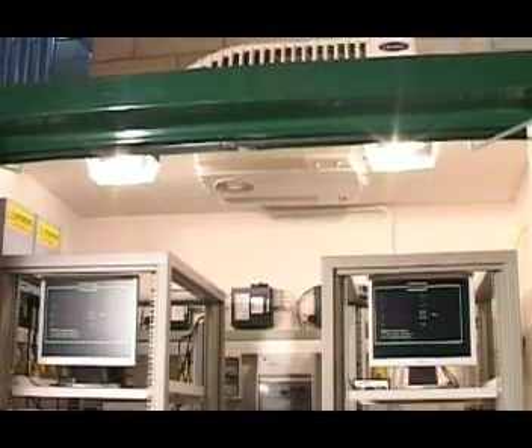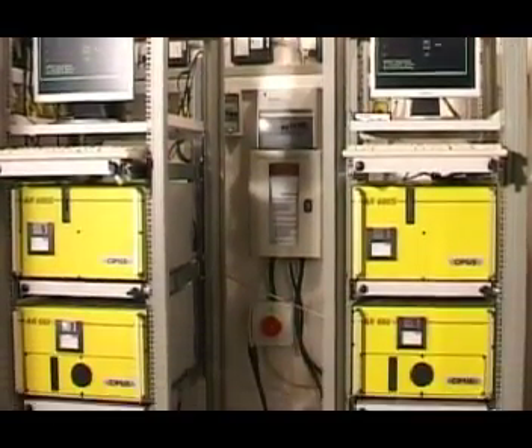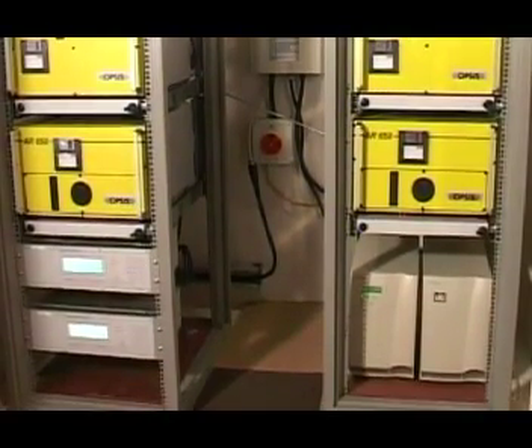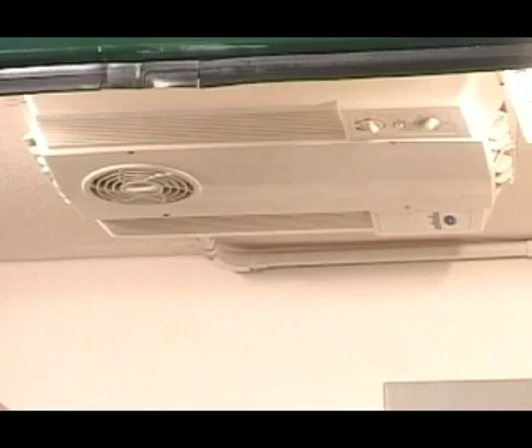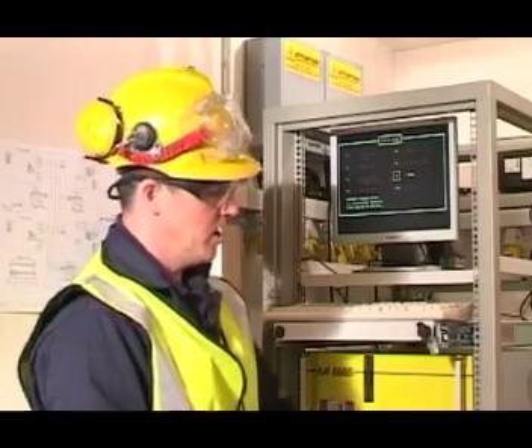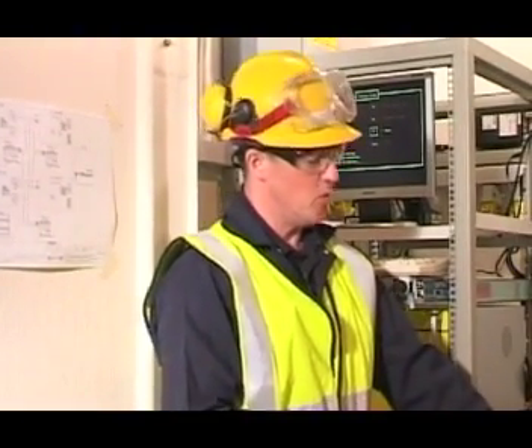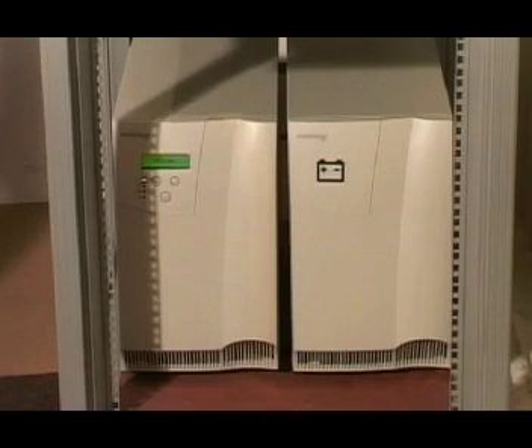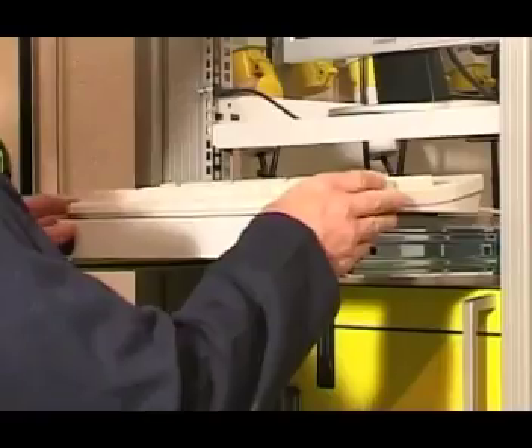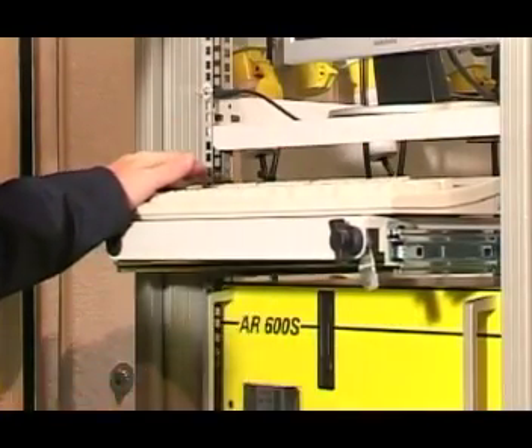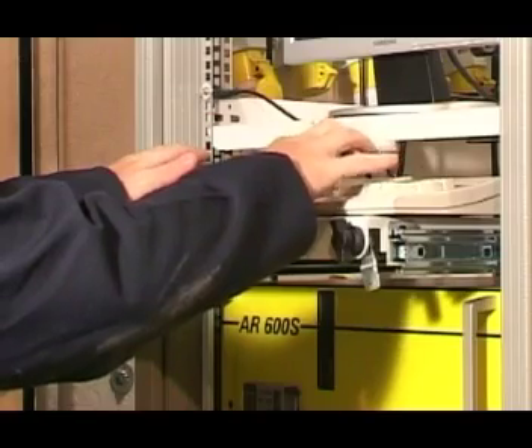Basically, the system comprises an air-conditioned cabinet. In the top of the unit here we have air filtering and air cooling to keep the machines in a nice, cool environment of say 24, 25 degrees. Obviously the environment is quite harsh outside, so the cooler we can keep it in here, the better for the instruments. The bottom of this cabinet has built-in UPS power backup, so in the event of the plant power going down, all instruments will be kept running, including air conditioning, via the UPS. We have 2 screens here and keyboards where we can control and perform service functions on all of the analyzers.